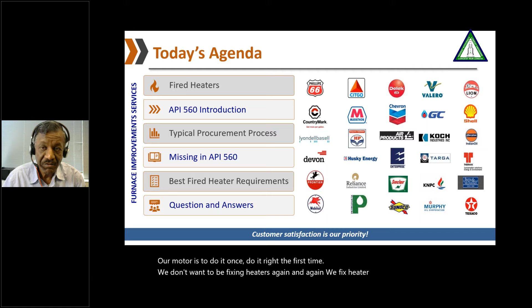So I'm presuming all of you are familiar with fired heaters. Fired heaters are high temperature heat transfer equipment. They are used wherever heat exchangers cannot be used. The chemical energy in the fuel gas or fuel oil is converted to thermal energy in flames and flue gases. The burners perform the task of combustion of fuel with air to produce high temperature flames. The radiant section is a place where the bulk of the heat is transferred by radiation. The convection section is a section after the radiant section where heat is recovered from flue gases by convective means. And the cold flue gases are vented through the stack for safe disposal.